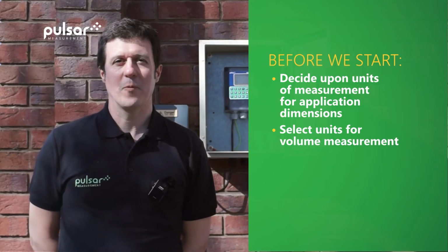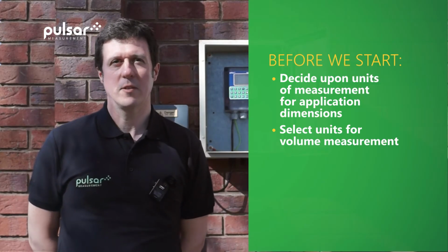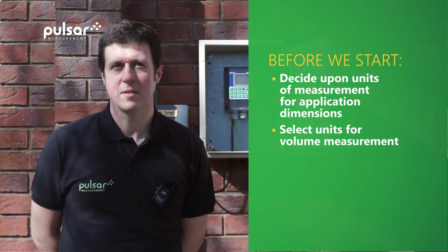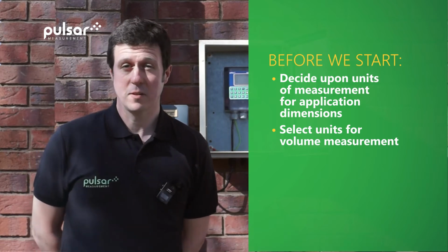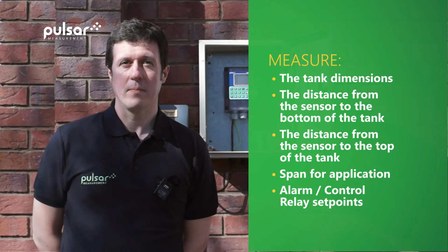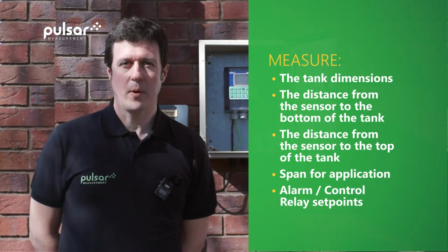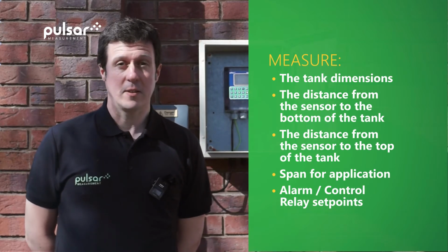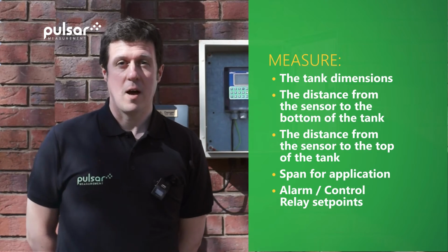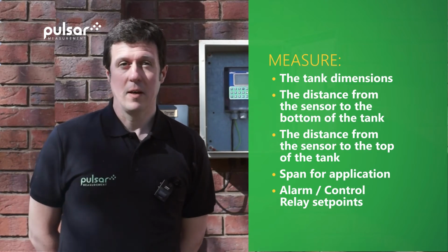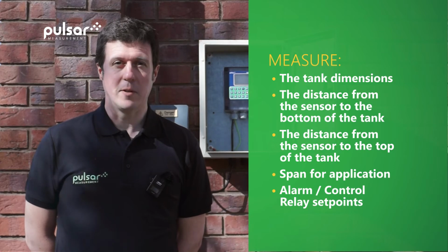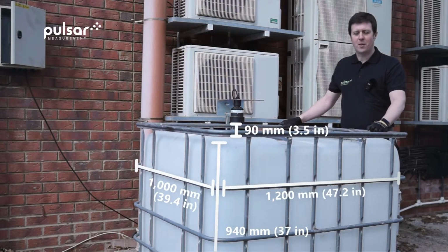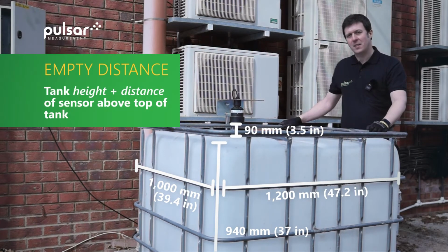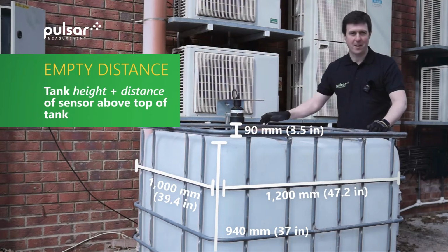Before we start, we'll need to decide upon the units of measurement for our application dimensions, the units for our volume measurement, the vessel dimensions, the distance from the sensor to the bottom of the tank, the distance from the sensor to the top of the tank, our span for the application, and any control or alarm relay set points. These are the dimensions of the IBC container. The empty distance can be calculated by adding the height of the tank to the distance of the sensor above the top of the tank.